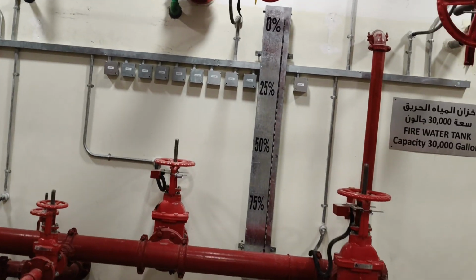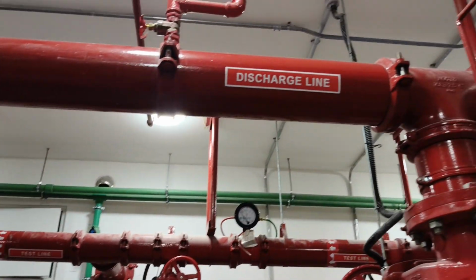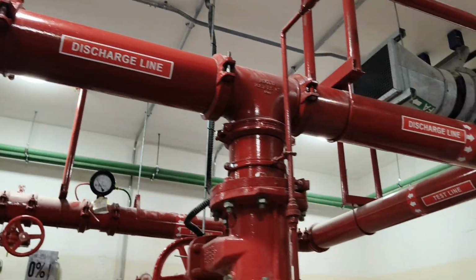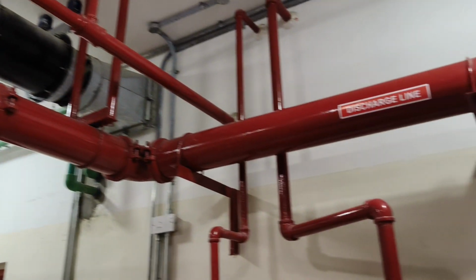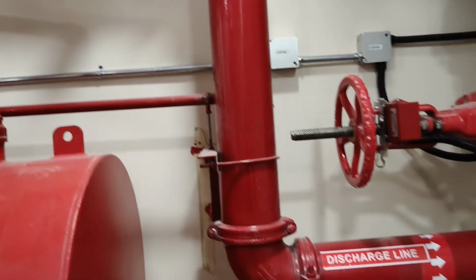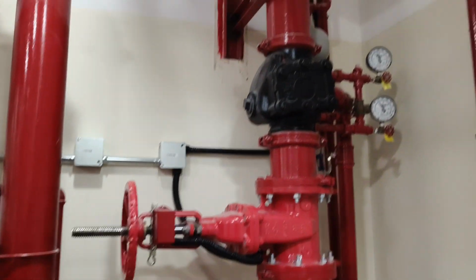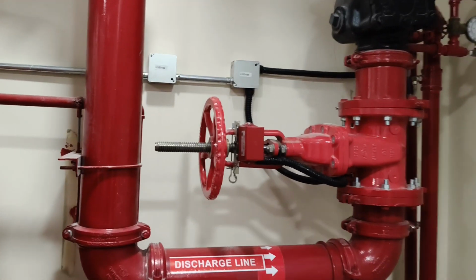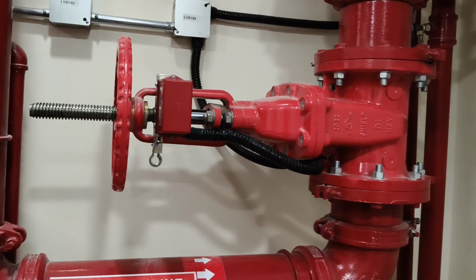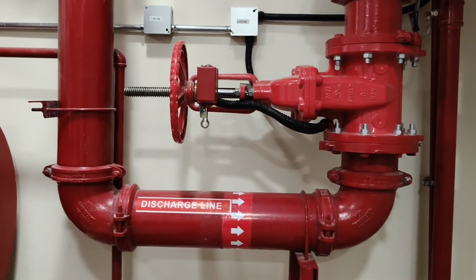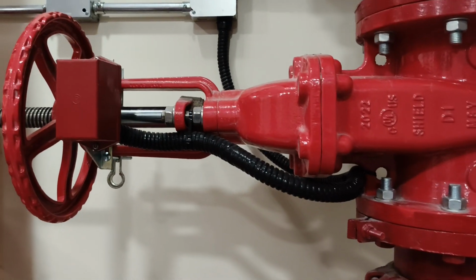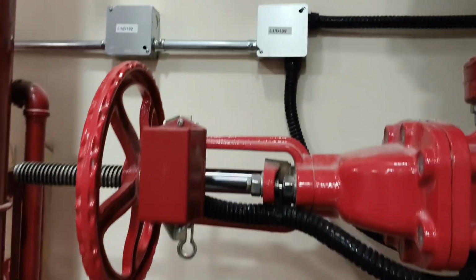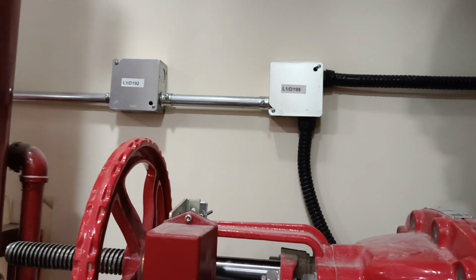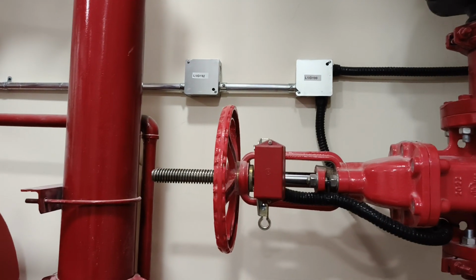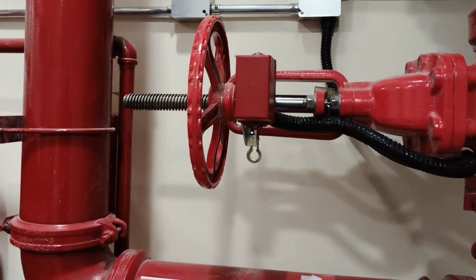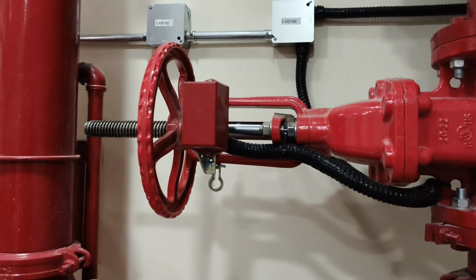okay, so going on now, you can see that this is the main discharge header, this is the discharge line, and it flows through the main discharge line directly to this discharge line, and from this pipe it comes directly to the alarm check valve. So this is the system line, and this is the main discharge valve. So in case of any testing, this is the valve that we are actually going to connect, and you can see that it's connected with tamper switches. All the valves that I showed you were connected, and the tamper switch is also connected to a module which is going to the fire alarm panel. All right, so if somebody tampers with this valve, an indication is going to be given to the fire alarm panel.